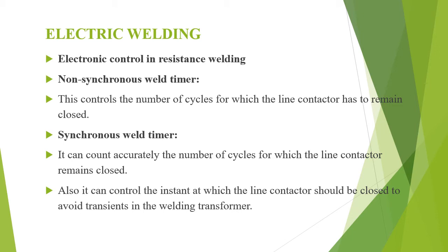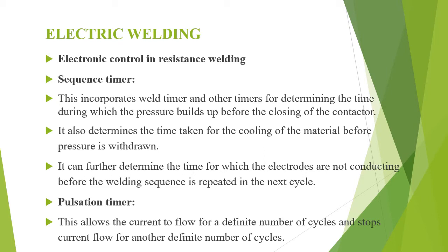Non-synchronous weld timer. This controls the number of cycles for which the line contactor has to remain closed. Synchronous weld timer. It can count accurately the number of cycles for which the line contactor remains closed. Also, it can control the instant at which the line contactor should be closed to avoid transients in the welding transformer.